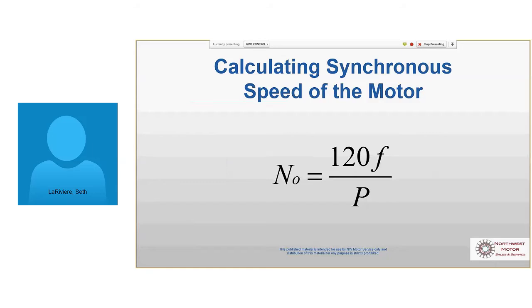You can tell the RPM of your motor if you take 120 times the frequency that you're running at, which normally is 60 hertz unless you're on a drive or something, divided by the number of poles. So we commonly in the motor world talk about motors as 2, 4, 6, 8 pole machines. 2 pole machines at 3,600, 4 poles at 1,800, 6 poles at 1,200.